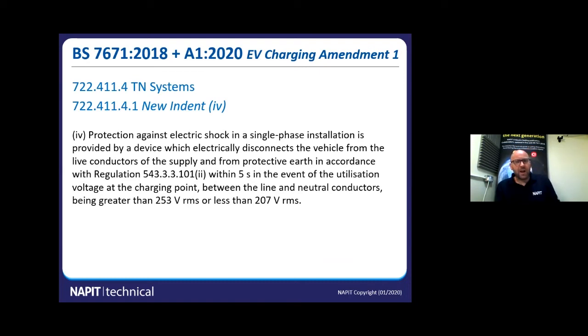That regulation there is because we're disconnecting the protective earth, which is something we don't often do. So that regulation requires that if you're disconnecting the earth, it doesn't get disconnected prior to the live conductors, and that it's reintroduced before or at the same time as the live conductors. So that's what that regulation is concerning there.